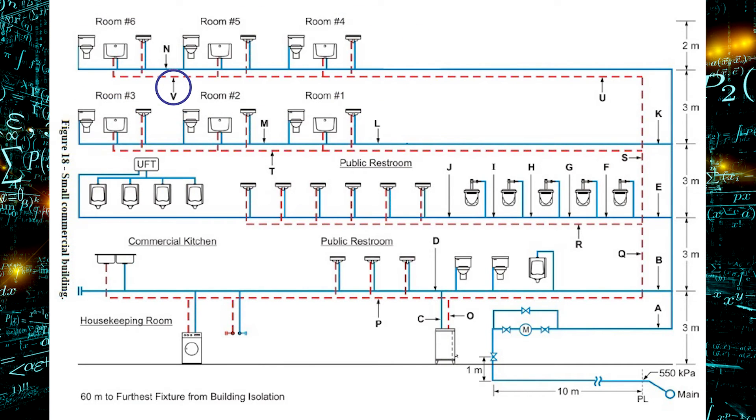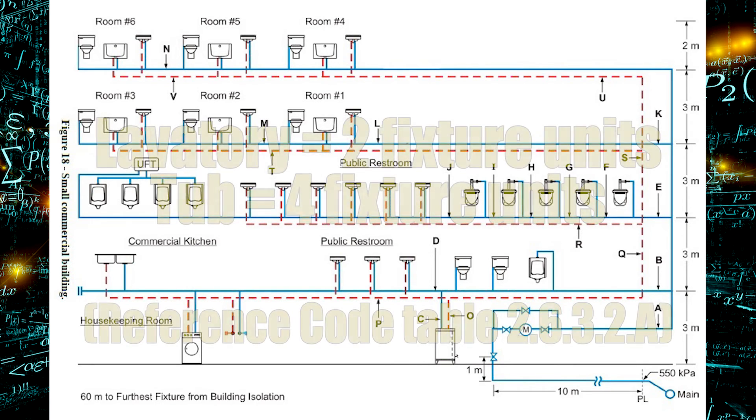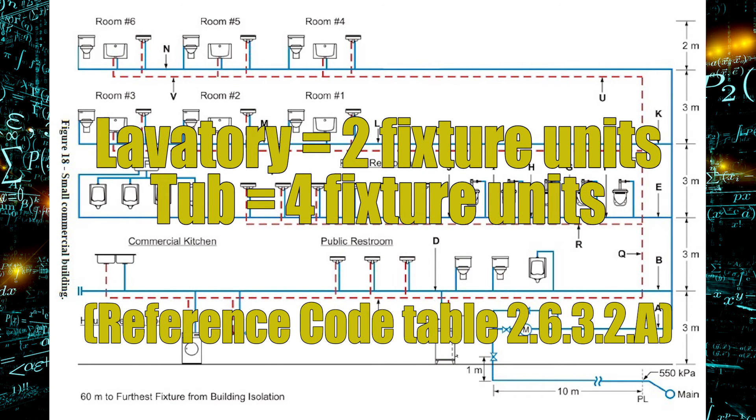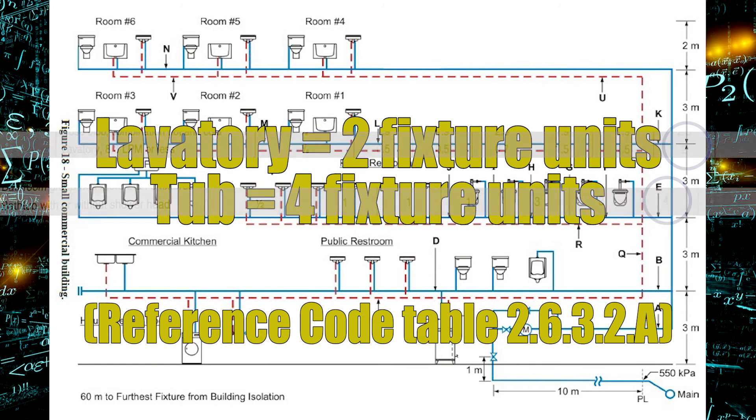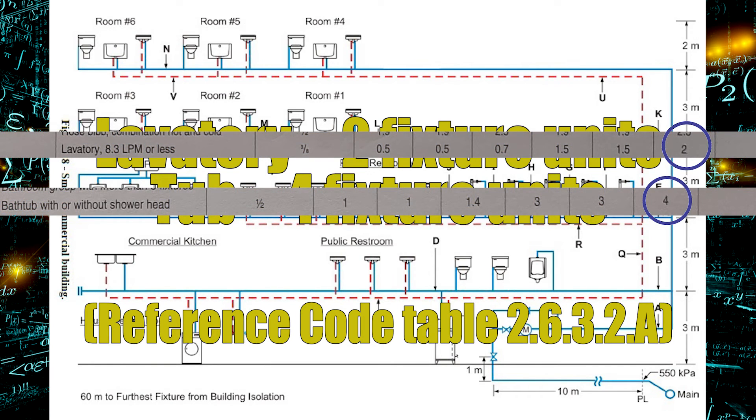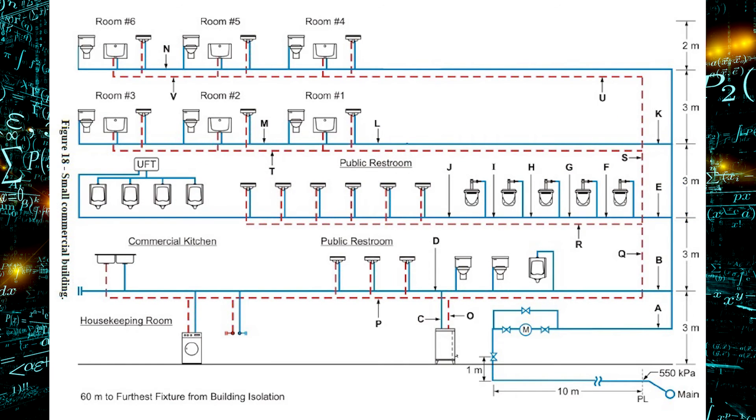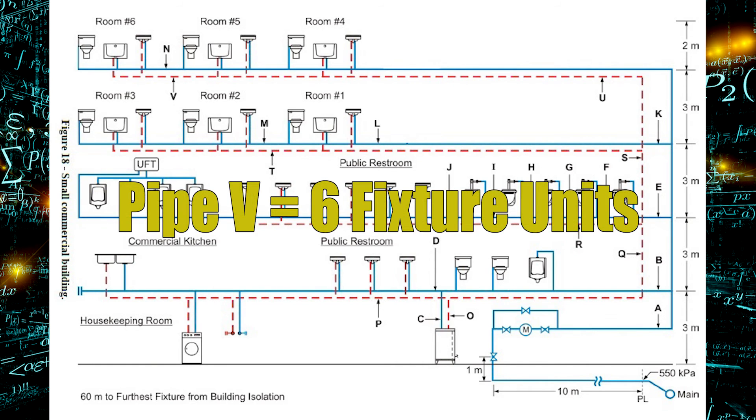And let's look at pipe V. Pipe V is the hot water piping, and it is serving a lav and a bathtub. All lavs in this building are 8.3 liters per minute or less, and the bathtub is just a bathtub with or without shower head. The lav is 2 fixture units. The bathtub is 4 fixture units, as can be seen on table 2632A right here. Pipe V needs to supply both the bathtub and the lav, so 4 plus 2 equals 6 fixture units.